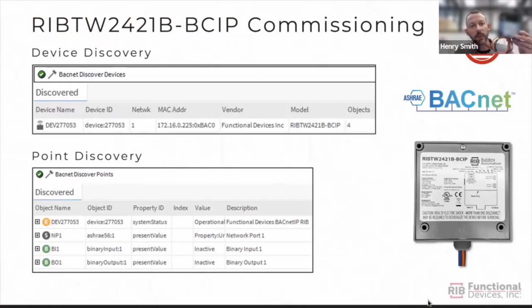Yeah, so I also brought with me a little demo here. Let me unblur this. What Ryan pointed out too, you couldn't really see on the top, but here's the Ethernet connection, and then your different indicator LEDs: binary input, relay, communication, a heartbeat, and then you've got another one for the LAN connection just for verification. And inside here we have a vulcanized fiber barrier, so it keeps all of your high voltage connections, your relay and your power connections down in this compartment, and then your low voltage for your 24 volt AC DC or your binary input are there and can be wired through a star grommet on the side of the enclosure.